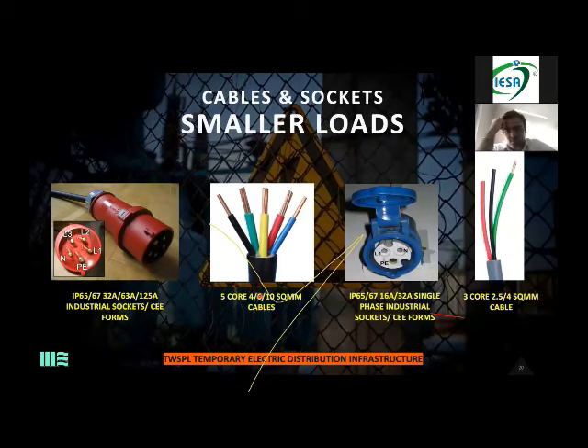Again, if you're using a 6 square mm wire, 5 core, it can take a load up to 20 kilowatts. If you're using 10, it can take a load up to 30 kilowatts. As we go ahead, the wire size changes and the socket size also changes, but the sockets only come up to 125 amps. These are for the smaller loads. When you say distribute the power, give me 30 kilowatts, give me 20 kilowatts, up to 60 kilowatts we can use these sockets.